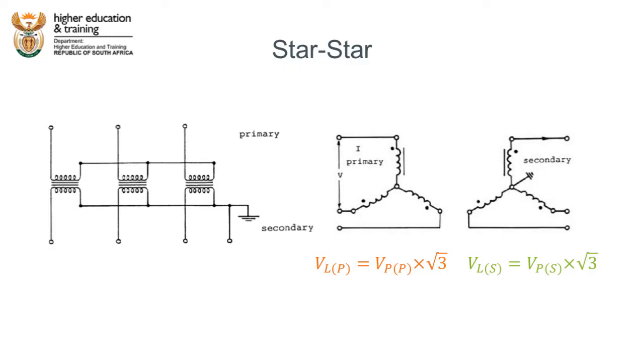That means we can connect three single-phase transformers or a three-phase transformer as star-star — connecting the primary side in a star configuration and the secondary side in a star configuration. Remember, the line voltage on the primary side equals the phase voltage on the primary side multiplied by the square root of three, and the same applies to the secondary side, because both are connected in a star formation.